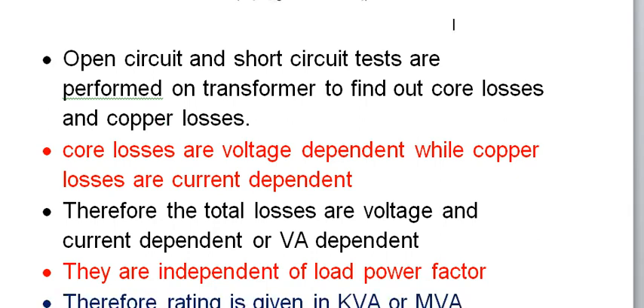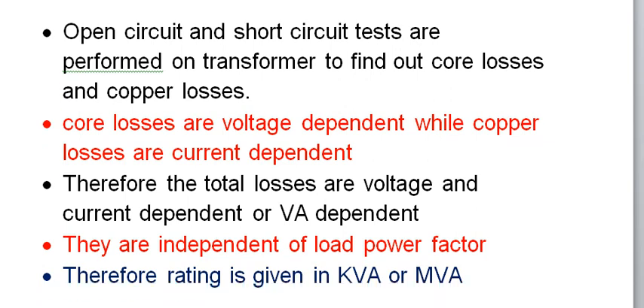When we say the losses are VA dependent, it means they are power factor independent — not dependent on the load power factor. The power factor of the transformer is governed by the load drawn through it, and it has no impact on the core losses or the copper losses. Therefore, transformer ratings are given in kVA or MVA.